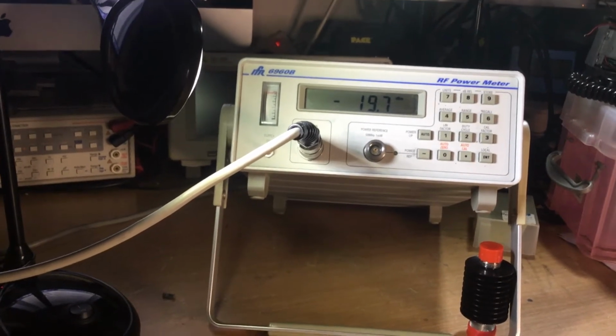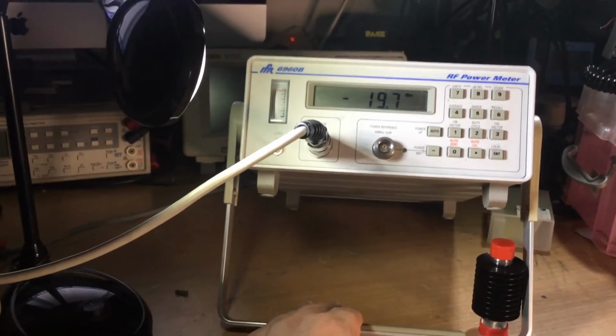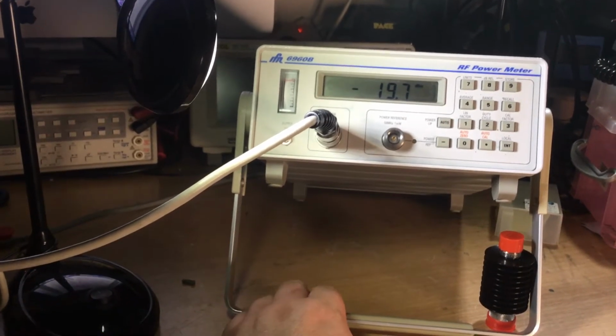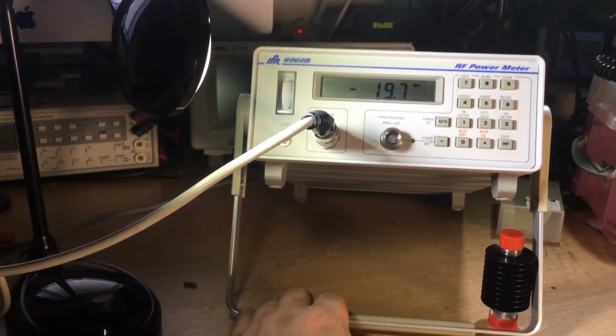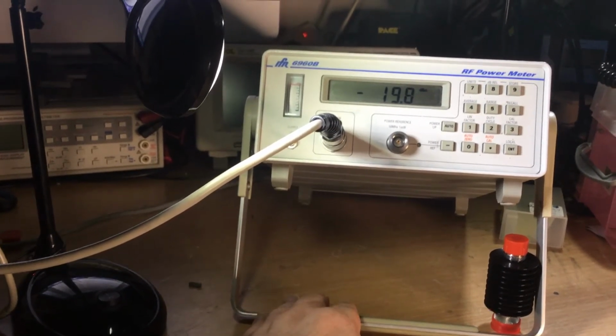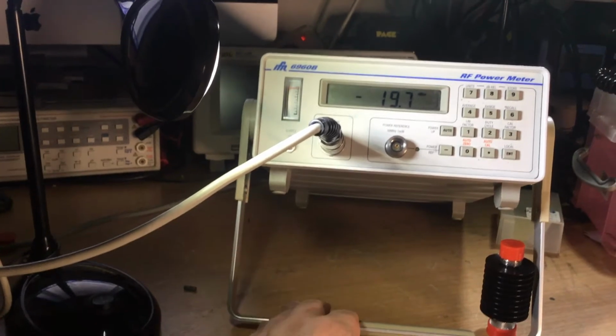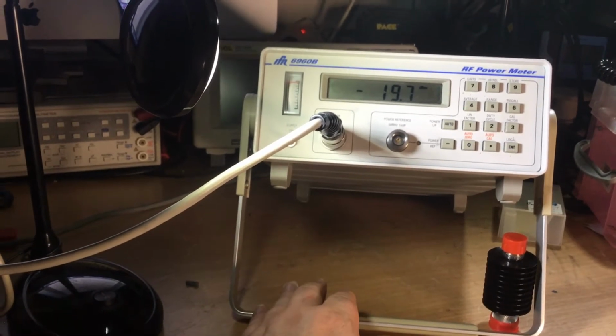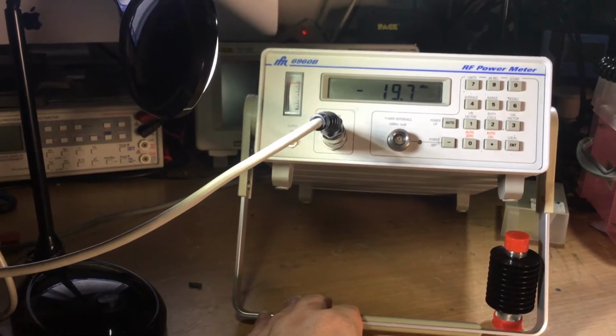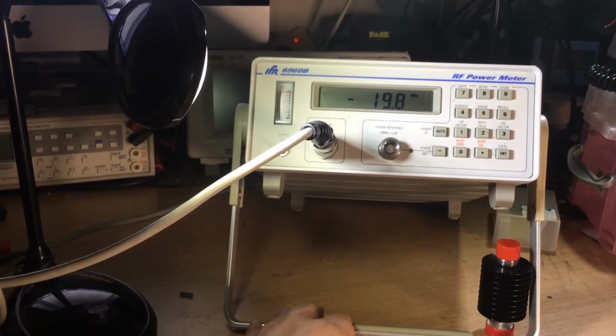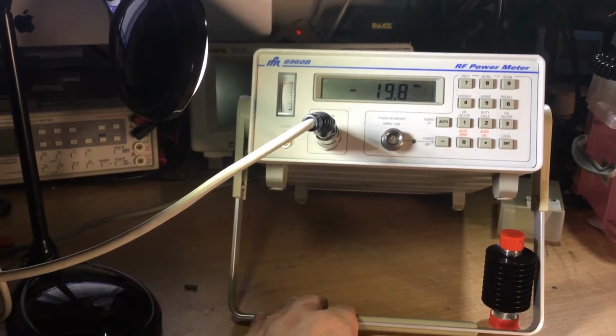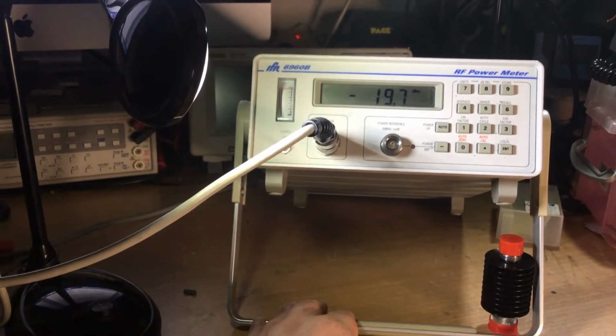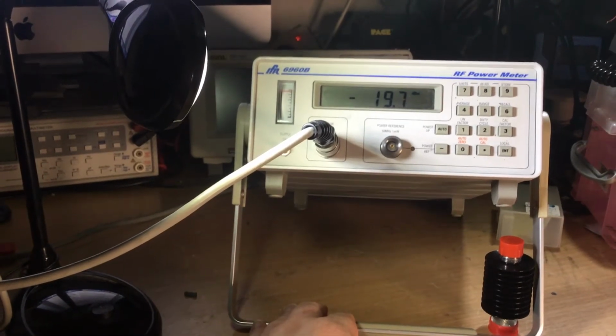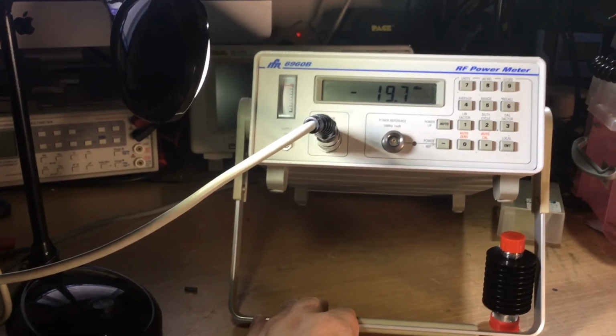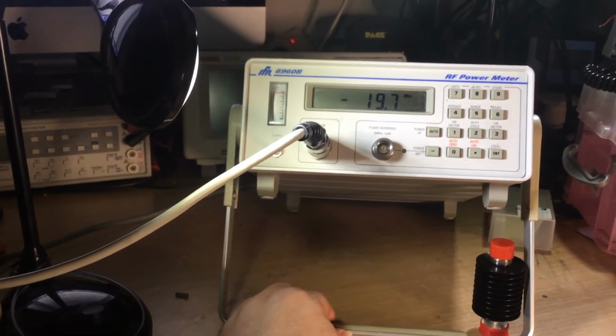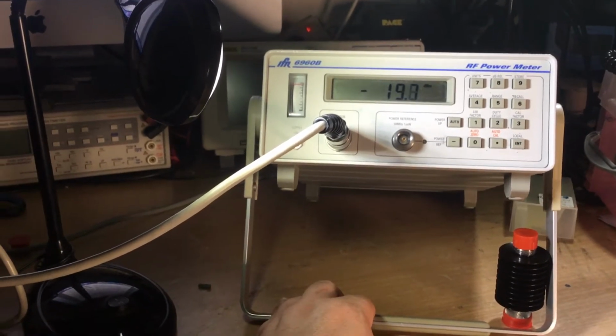The precision calibration attenuators: it says the 6920 series of high sensitivity power sensors are supplied with a precision 30 dB attenuator for calibrating to the internal power reference. These attenuators have an accuracy of plus or minus 0.05 dB at 50 MHz to provide high calibration accuracy. Duty cycle correction: although the 6960B is a true average power measuring instrument, it may still be used for pulsed power measurements. The duty cycle of the signal to be measured may be entered in the range 100 to 0.001%. The power meter calculates the peak power by dividing the measured average power by the duty cycle.